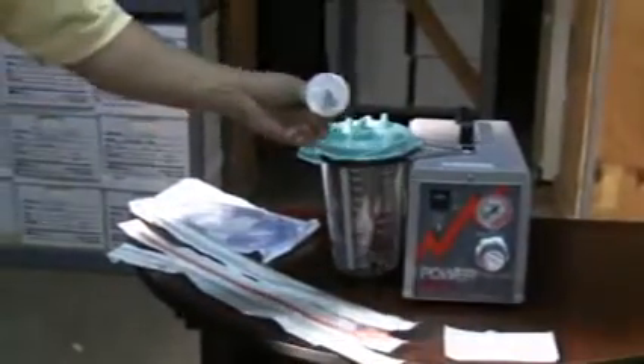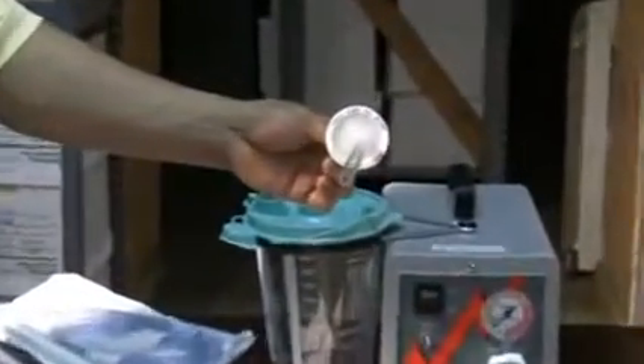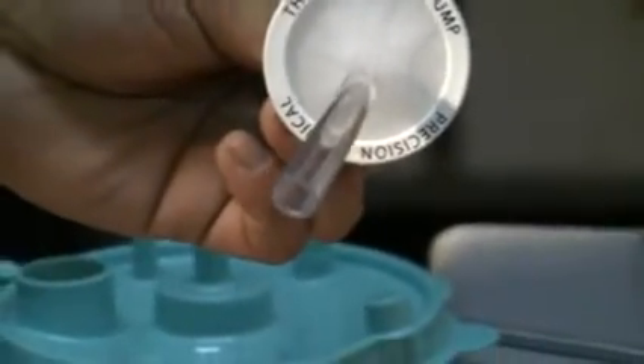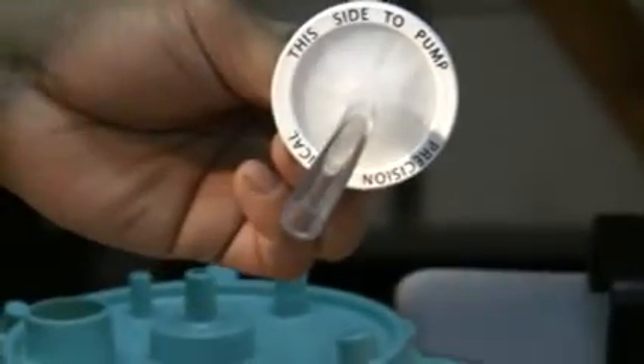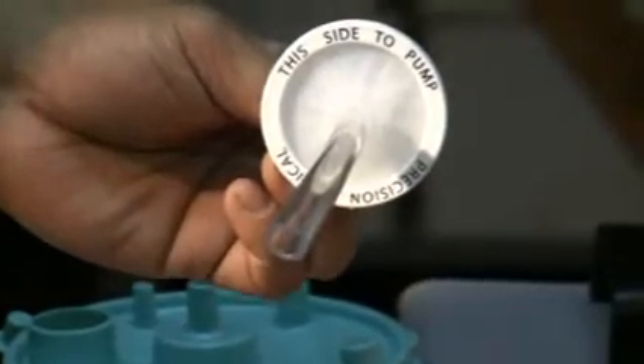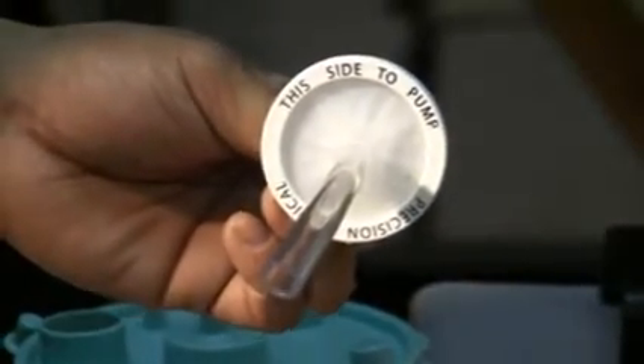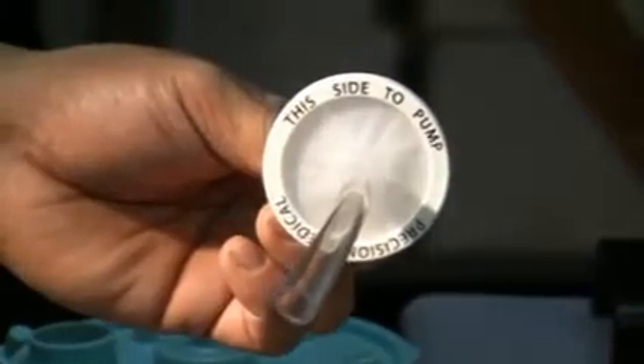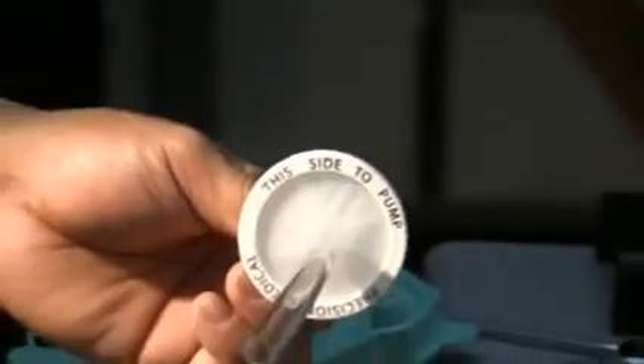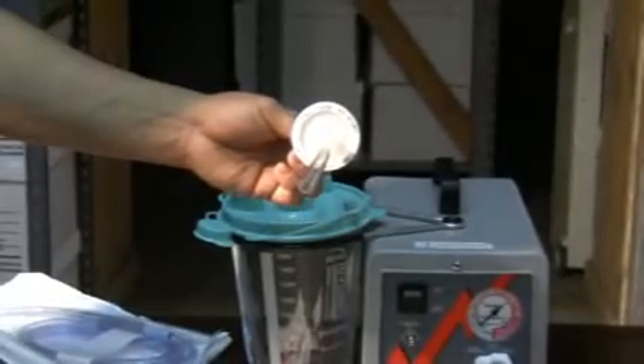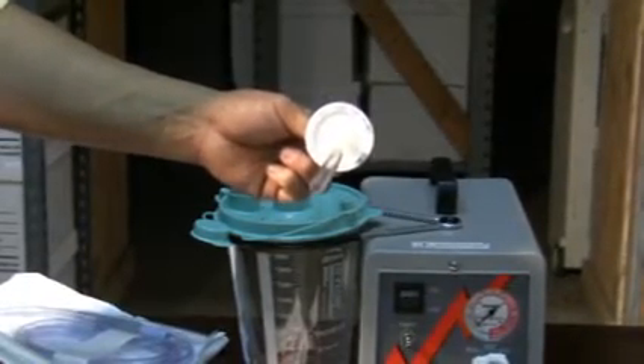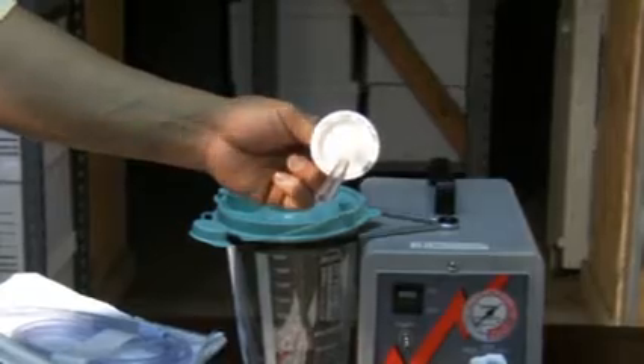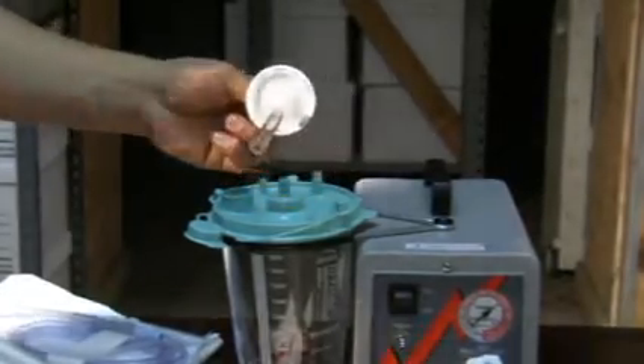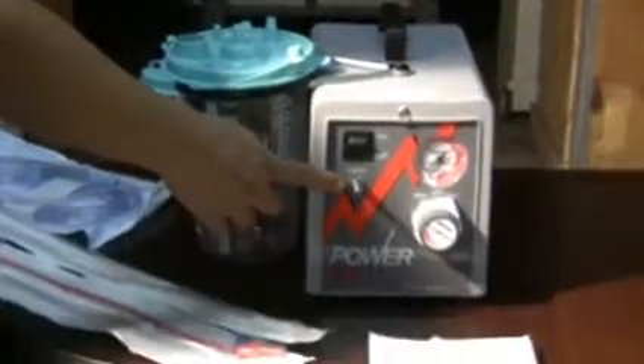We will get our hydrophobic filter, which is directional. It also says "this side to pump," which should always be the side connected facing towards the pump. If the hydrophobic filter is inverted when it's connected to your intermittent suction machine, you may get no vacuum or no response from your machine. So the side that says "this side to pump" should be placed on the outlet located on the front of your intermittent suction machine.